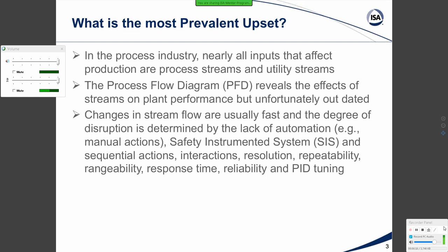But it really starts out perhaps as seeing more noise, but then the signal gets very erratic and disruptive. And we have to keep that in mind when we consider doing feed-forward control, particularly since we're thinking of flow as being the primary feed-forward signal. And so we need to try and improve the rangeability.